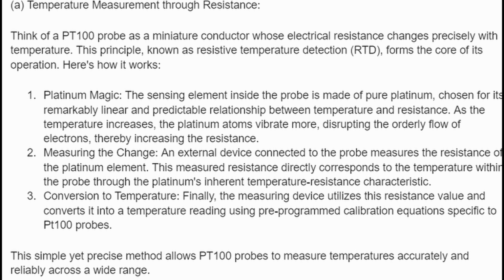An external device connected to the probe measures the resistance of the platinum element. This measured resistance directly corresponds to the temperature within the probe through the platinum's inherent temperature resistance characteristic. 3. Conversion to temperature. Finally, the measuring device utilizes this resistance value and converts it into a temperature reading using pre-programmed calibration equations specific to PT100 probes. This simple yet precise method allows PT100 probes to measure temperatures accurately and reliably across a wide range.